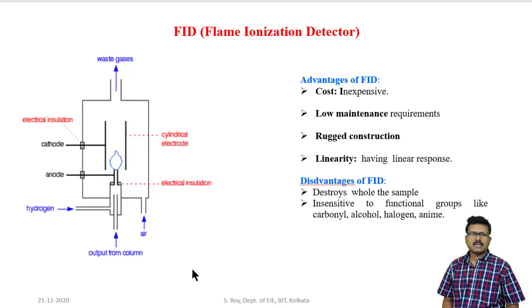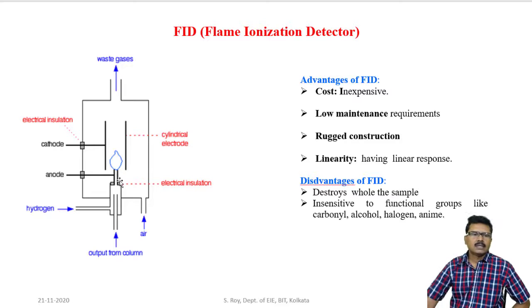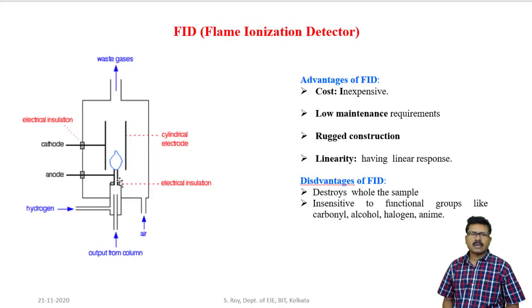Flame ionization detector is inexpensive to operate and acquire, with low maintenance requirement apart from cleaning and replacing the jet. Regarding construction, it is rugged and relatively resistant to misuse, and it gives linear output. The main disadvantage is that it destroys the whole sample — all the sample coming from the column is destroyed by the flame — so if we want to send the product to a mass spectrometer for further analysis, we can never use flame ionization detector.